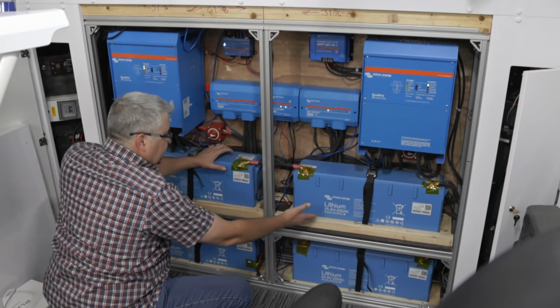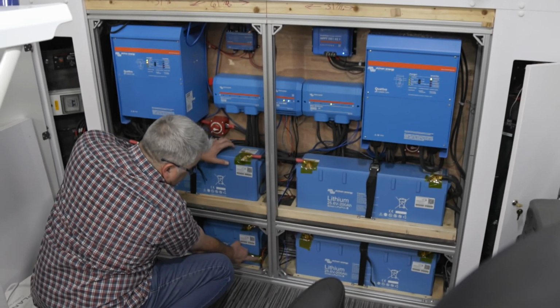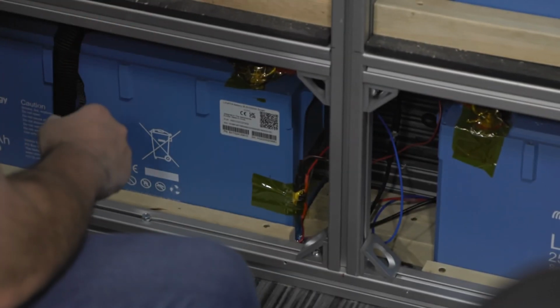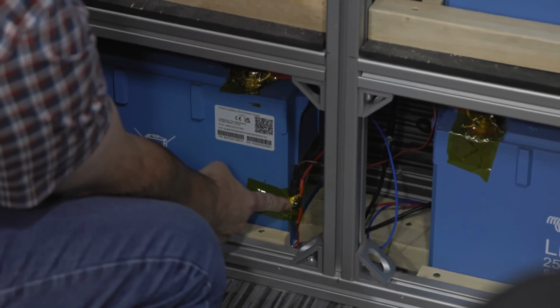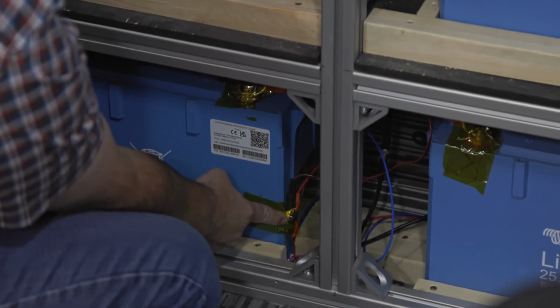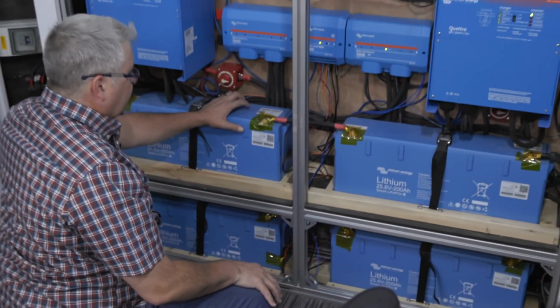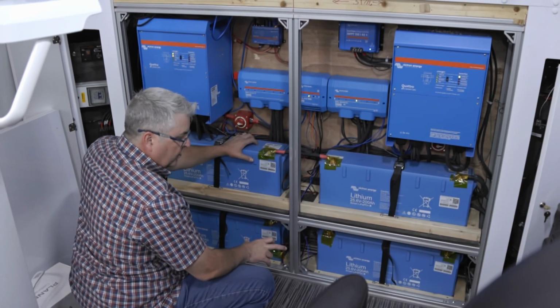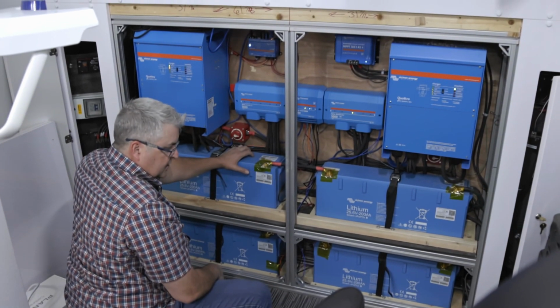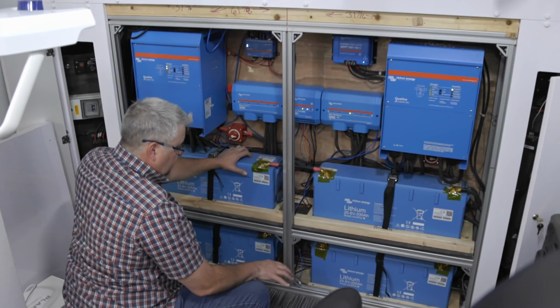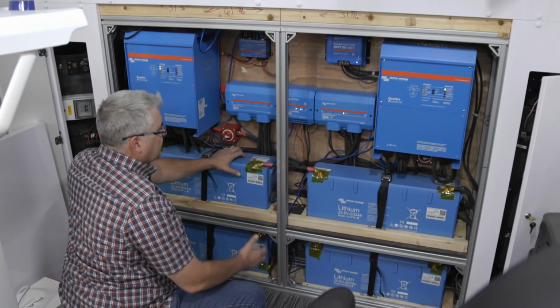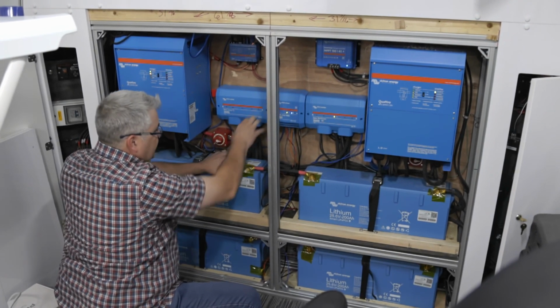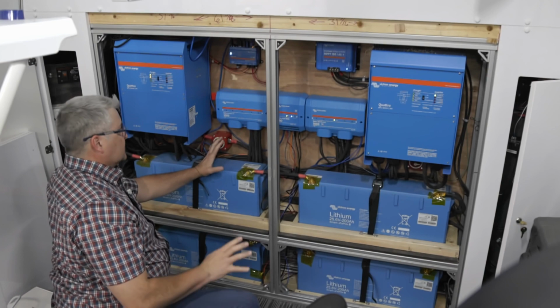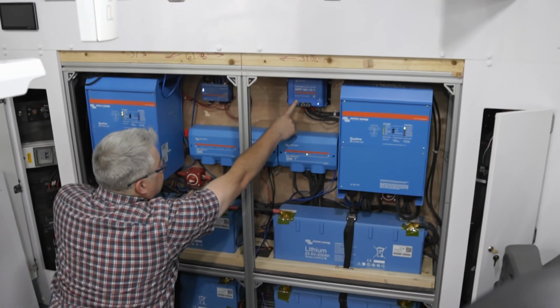There are heating pads under each battery that are thermostatically controlled, with the thermostat attached to one of the bottom batteries. It's kind of set and forget. It happens automatically. If the thermostat gets below about 50 degrees, it will kick on and start warming the batteries. That way, if the vents are left open in the winter time, hopefully the batteries don't get so cold that they tell the BMS that they won't charge. When the batteries get really low, very cold, or very hot, those things can cause this BMS to open up the contactor and say, hey, you need to figure out what's going on.